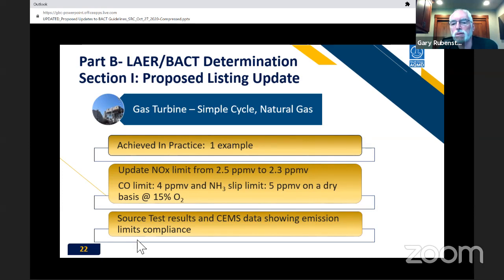Bahar, this is Gary. This one, it's a little confusing because the listing shows BACT limits for VOC and ammonia, as well as for NOx and CO. But the compliance demonstration section, section 6, shows the CEM results for CO and NOx, and it's left unclear as to whether there was a CEM for VOC and ammonia. I suspect there is not, or whether those were verified by compliance tests. So I'd suggest that you clarify that the VOC and ammonia values were confirmed by compliance tests rather than by CEM. For compliance tests, okay.